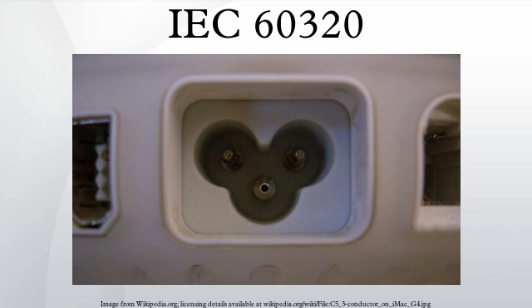Selection of a coupler depends in part on the IEC appliance classes. Class I appliances must have their chassis connected to electrical earth and require a coupler with earthing. Class II double-insulated electrical appliances do not require a safety connection to electrical earth and can use a coupler with only two circuit conductors. Connectors are also classified according to the method of connecting the cord, either as rewirable connectors or non-rewirable connectors. In addition to the limiting values, the standards define further general criteria such as withdrawal forces, testing procedures, the minimum number of insertion cycles, and the number of flexings of cords.